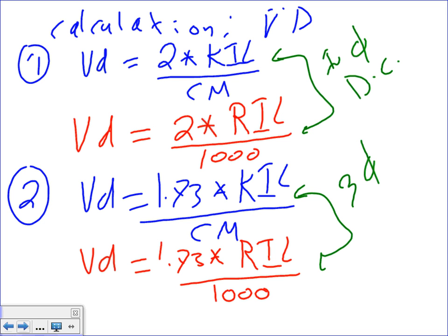And aluminum, 21.2. These two factors, guys, are material-oriented factors, depend on temperature, and they change from one location to another. For the most part, let's set these as the criteria: K for copper, Cu, is 12.9, and K for Al is 21.2.